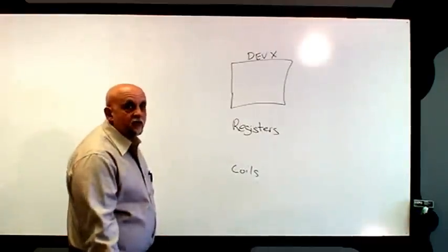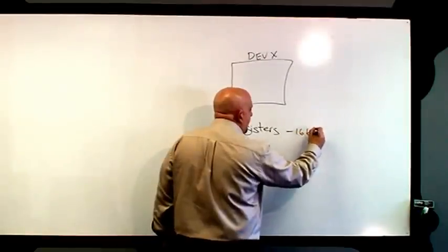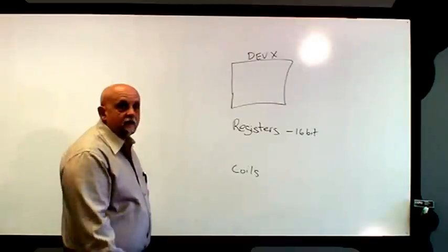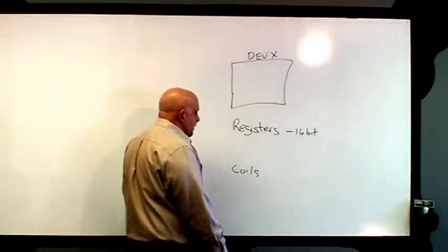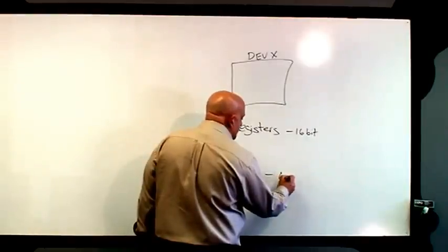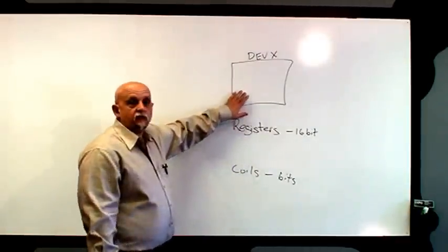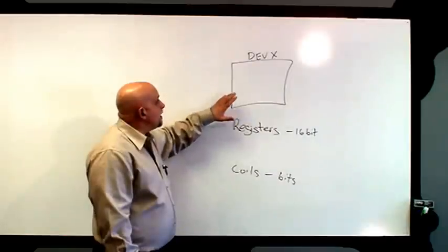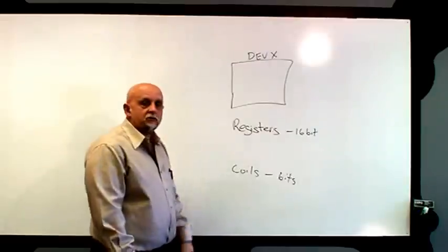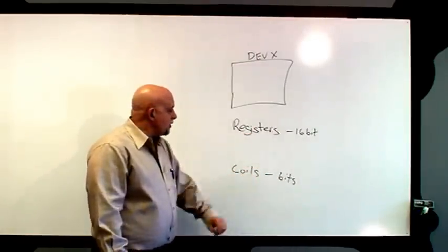So what are registers? Registers are nothing more than 16 bits of unsigned data. Now, 16 bits is the standard word size for most computer systems. Coils are nothing more than single bits. So that device, from the point of view of the Modbus network and the Modbus master, has a bunch of registers and a bunch of coils. The registers are simply 16-bit values; the coils are bits.